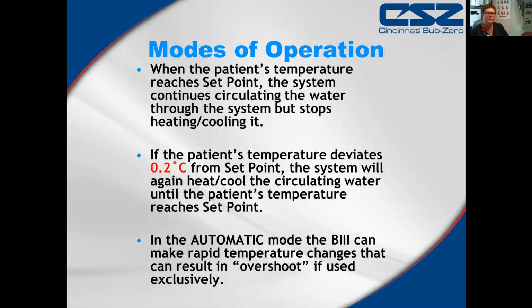So when the patient's temperature reaches the set point, so what we have said, the system continues cycling the water through the system, but it stops heating and cooling. So once it's reached, the machine just continues to monitor. And if the patient's temperature deviates 0.2 degrees from the set point, then the system will either start warming or cooling depending on the need. The automatic mode of the Blanketrol III can really create a rapid drop or a rapid rise in temperature. So overshoot is what we are fearful of, and that's why we use it for the induction phase only.